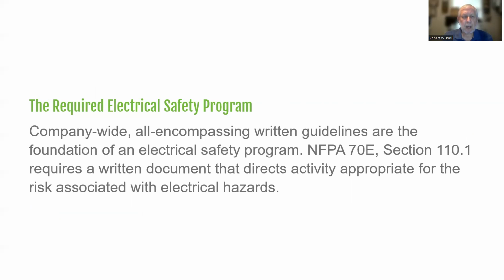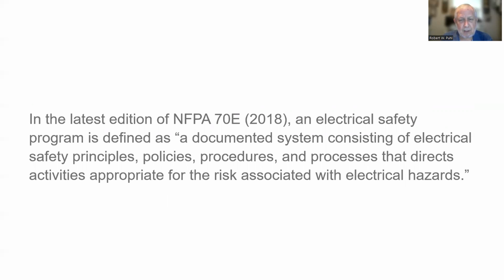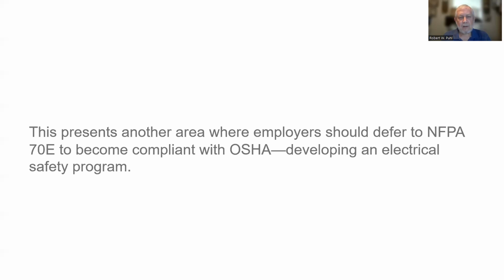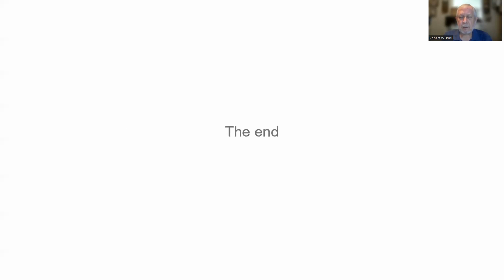The required electrical safety program: company-wide, all-encompassing written guidelines are the foundation of an electrical safety program. NFPA 70E, section 110.1, requires a written document that directs activity appropriate for the risk associated with electrical hazards. The latest edition, NFPA 70E 2018, defines an electrical safety program as a documented system consisting of electrical safety principles, policies, procedures, and processes that directs activities appropriate for the risk associated with electrical hazards. This presents another area where employers should defer to NFPA 70E to become compliant with OSHA in developing an electrical safety program.